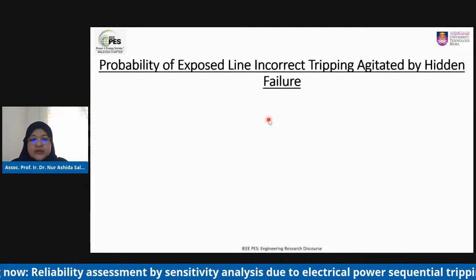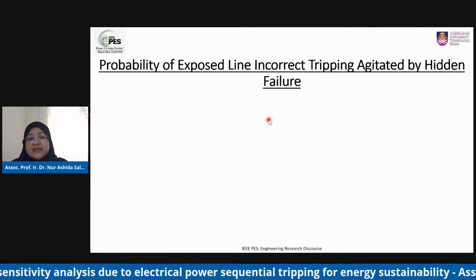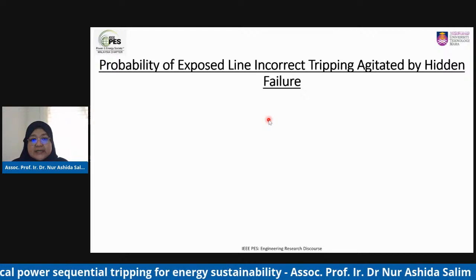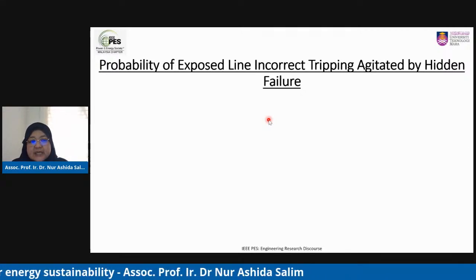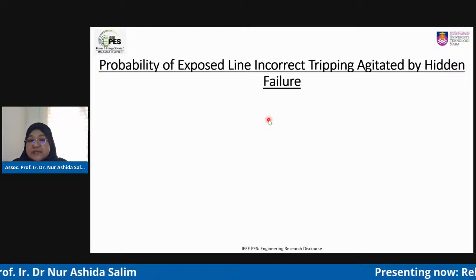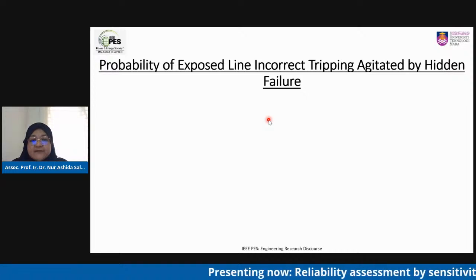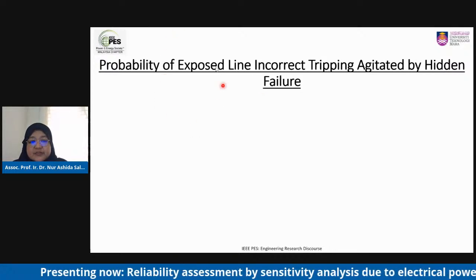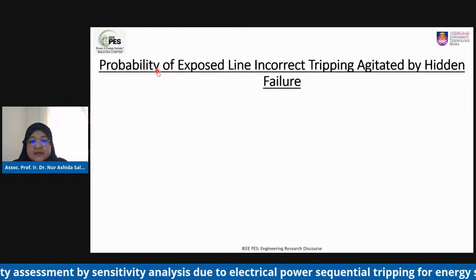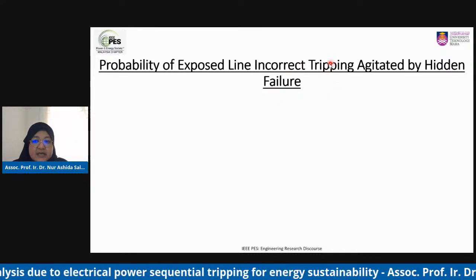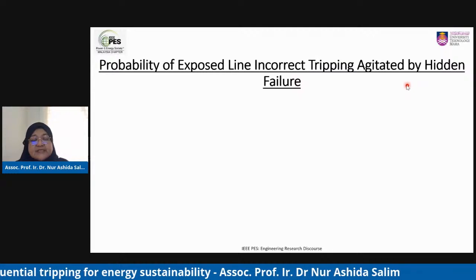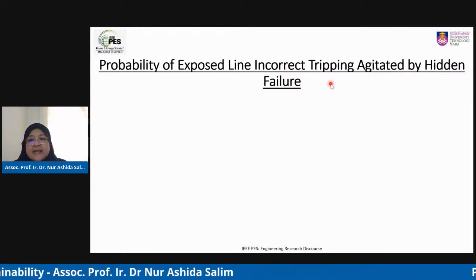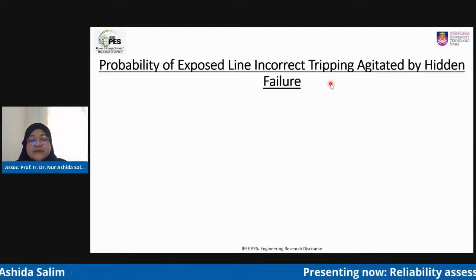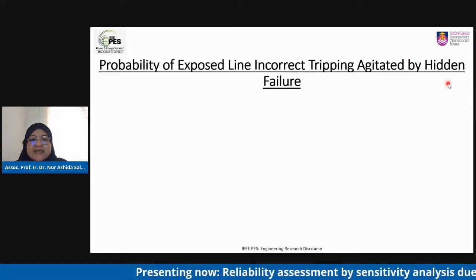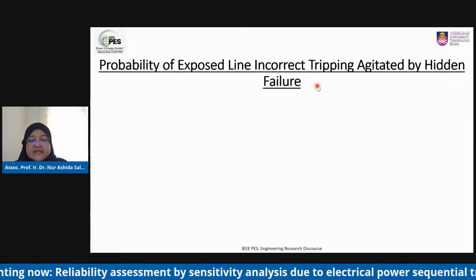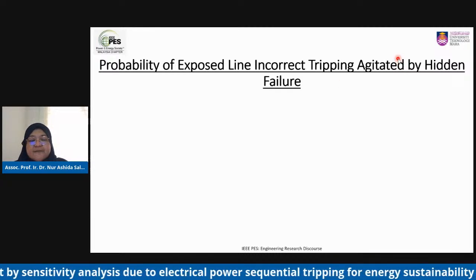All right, so I did mention just now regarding the risk assessment that we are going to look into the probability. I will explain how to model this probability to identify whether the exposed line and also the exposed generator will trip. For the generator, it depends on the critical clearing time, but for the exposed line it is due to the model of probability. The probability of an exposed line incorrectly tripping is due to hidden failure of the protection system. Hidden failure of protection system, in the second series of the IEEE PES engineering research discourse, has been explained by Dr. Lutfi. For those who missed that part of the explanation, you can watch it back on the IEEE PES YouTube channel.